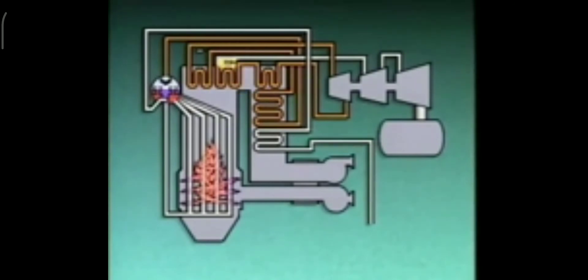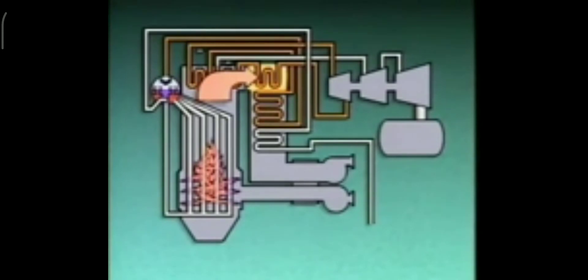An attemperator, located at the beginning of the secondary reheater, is used to control the final temperature of the superheated steam leaving the secondary reheater. The attemperator sprays water into the steam flow if the steam gets too hot. The secondary reheater in this example can also be classified as a radiant reheater, because it is located in a line of sight with the boiler flames and receives most of its heat by radiation from the flames. The primary reheater is located farther from the flame, and it receives most of its heat by convection from the hot combustion gases, so it can be classified as a convection reheater.